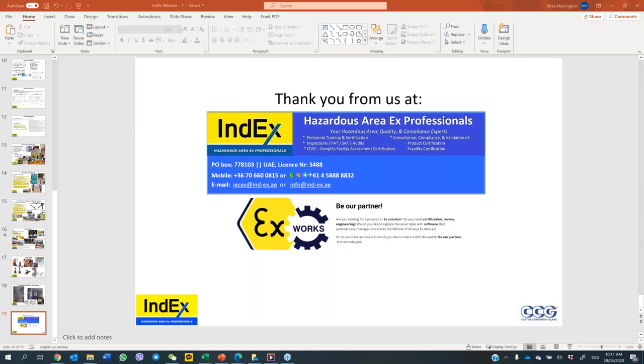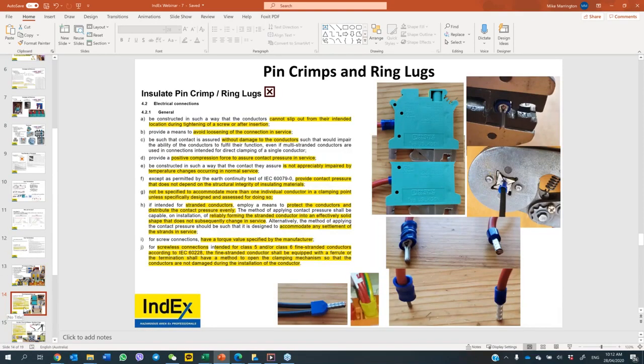HVAC is my favorite, somebody said, for terminations. Yeah, because you could be looking at Ex d, p, i, e, oh, lots. If an Ex e terminal box, must you use ferrules instead of insulated pin crimps? I showed you the standard. It clearly defines that. So this one with all the highlighted sections, it'll show up on my screen. There you go.